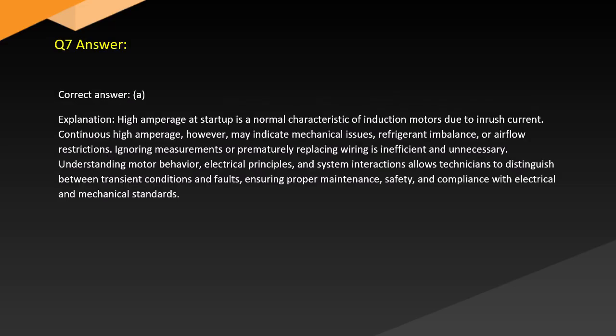Answer. Correct answer: A. Explanation. High amperage at startup is a normal characteristic of induction motors due to inrush current. Continuous high amperage, however, may indicate mechanical issues, refrigerant imbalance, or airflow restrictions. Ignoring measurements or prematurely replacing wiring is inefficient and unnecessary.